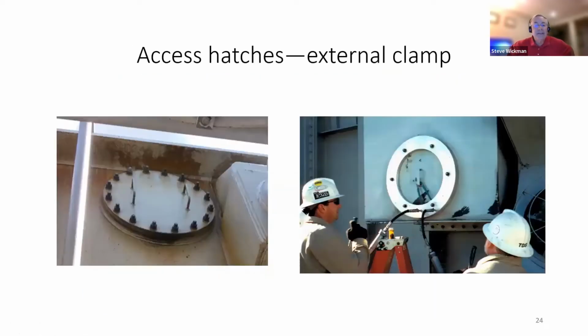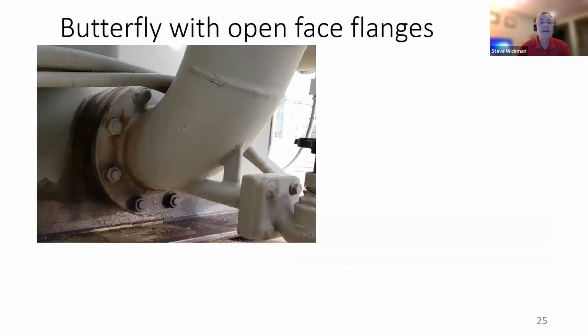Those access hatches, you saw that picture on the left, and the picture on the right is an access hatch that is at the base of a bushing pocket on a large transformer. And you see where the clamp has been put in place, and the technicians are pumping the sealant compound into that clamp. And again, there's a very good possibility this transformer was, I mean, energized, was very much in service, energized at the time that this work was being performed. And it's down at ground level. We're far away from the live components up on top.